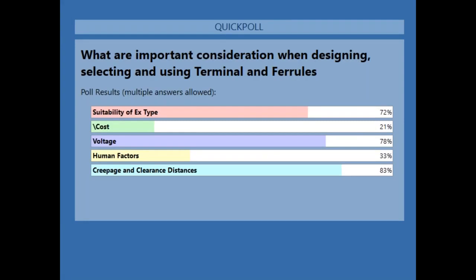So 83% say creepage and clearance distances. Now, guys, the answer is all of them. It shall be 100% across the board. What are important considerations? Well, human factors. Is there a high chance for faults, like with insulated pin crimps? Is there problems with suitability for EX type, like insulated pin crimps? Is there problems with creepage and clearance distances, like with insulated pin crimps?